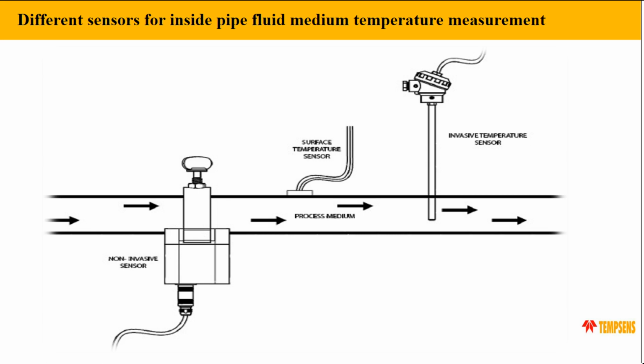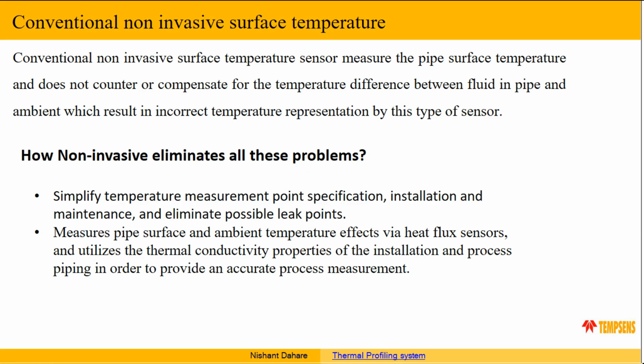One more thing is the surface temperature sensor. This is a non-invasive method, but its accuracy is very poor, mainly for two reasons. Conventionally, a non-invasive surface temperature sensor measures the temperature of the pipe's surface, which does not compensate for the temperature difference between the ambient and the fluid inside the pipe. It assumes the process temperature equals the surface temperature, and does not compensate for the effect of ambient conditions on the surface temperature. Hence its accuracy is very low compared to invasive thermowells and our non-invasive clamp sensor.